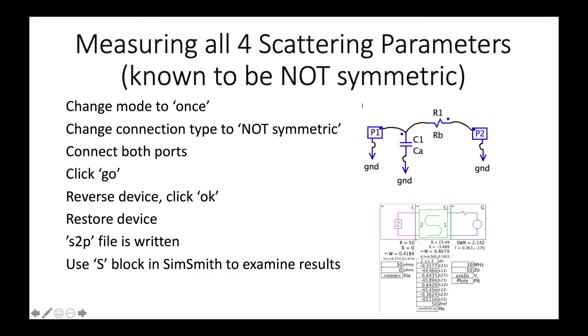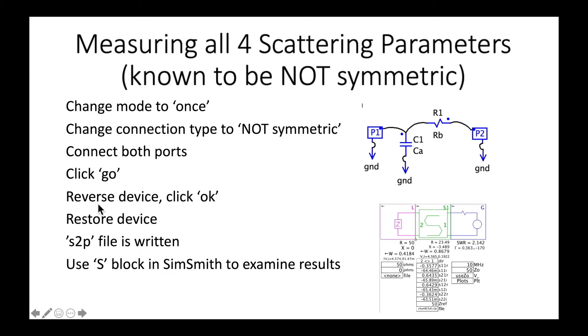And now I'm going to measure all four parameters of a non-symmetric device. Notice that I'm going to have to reverse the device. So I'm going to change the mode to once, I'm going to hit NOT symmetric, I'm going to connect to both ports, I'm going to hit go, I'm going to reverse the device, and then I'm going to examine the result.